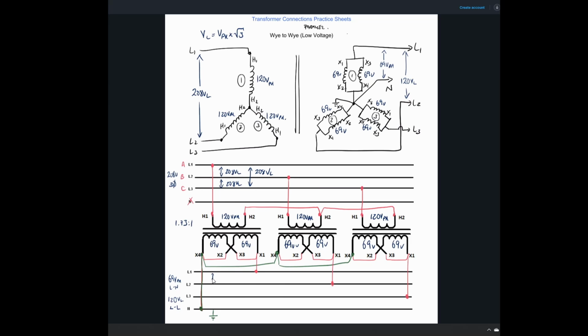So between these guys, 120 volts on the line, these guys, beautiful. And then from any line to neutral, we're going to have 69 volts as our phase value there. So some funky voltages that you'd never see out in the field. And the reason why we're getting those voltages is simply because we only have one source voltage here at 208.